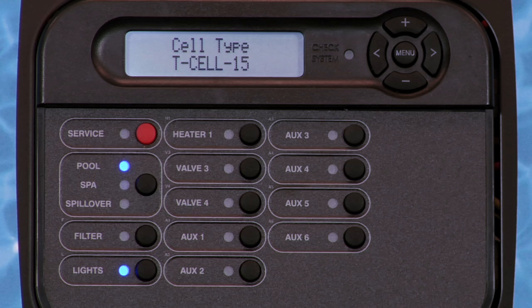T-cell 15 is the default cell type and will be displayed and flashing. The cell type, like all flashing values on the display, can be changed using either the plus or minus key. ProLogic gives you the flexibility to choose the right cell type for a particular application.